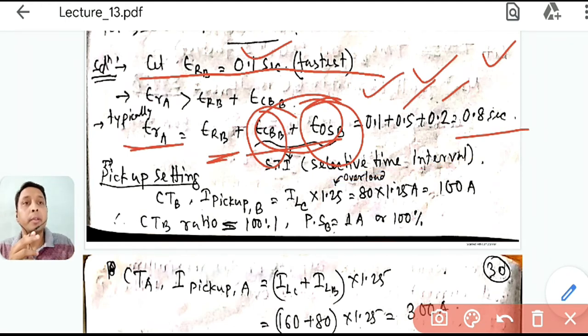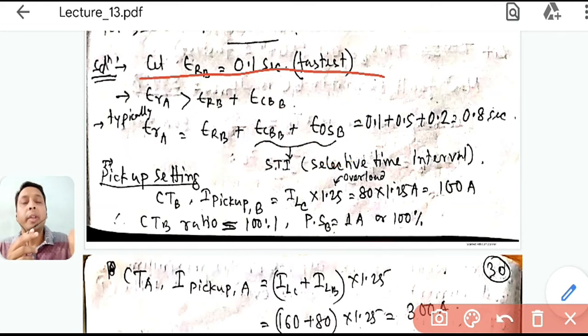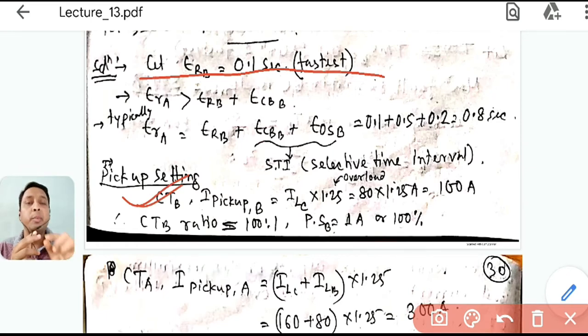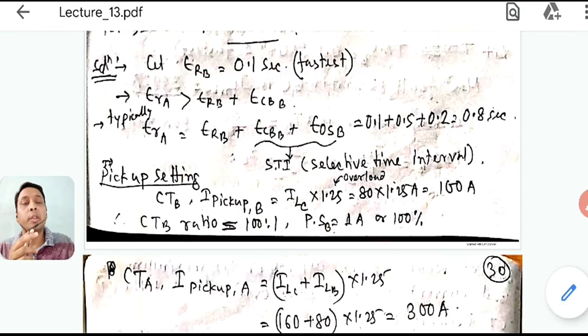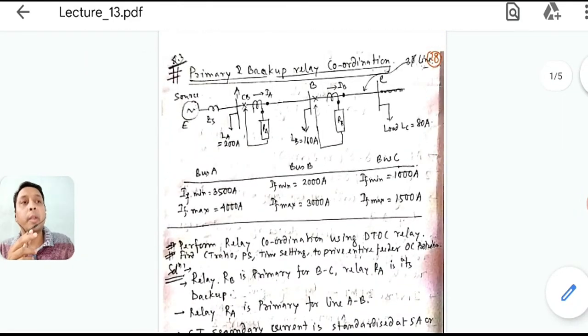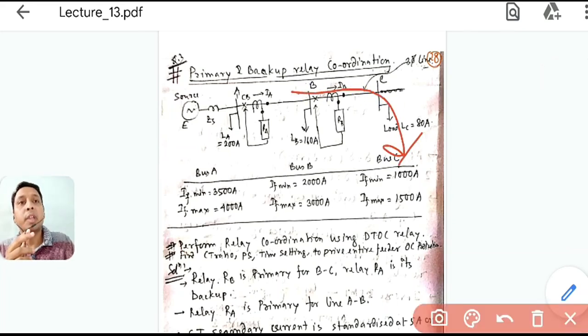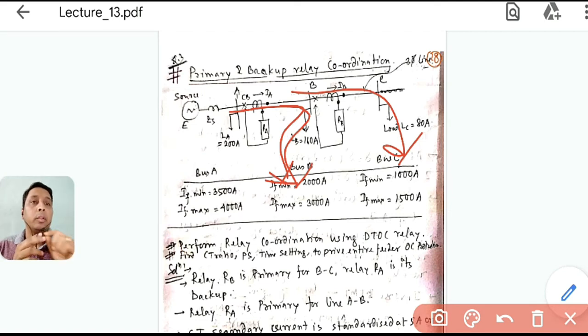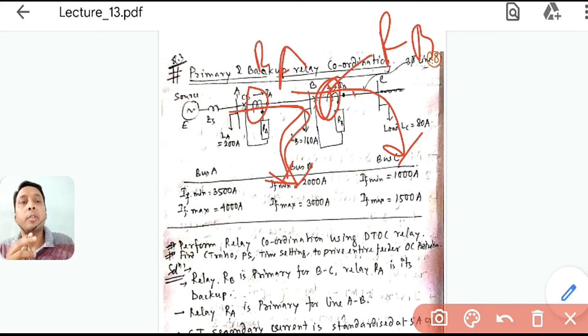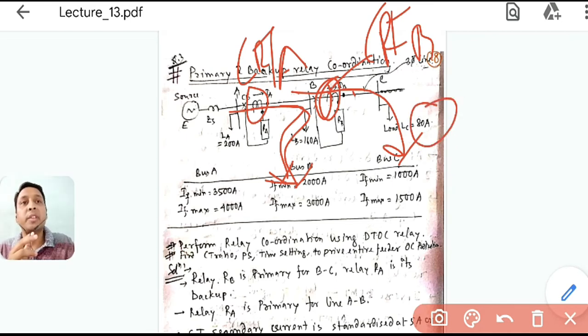Now let us calculate the current settings. For CT of relay B, we need to identify the normal load current passing through it. The load current flowing through relay B is only the current in the BC section, not the current flowing through relay A's section.